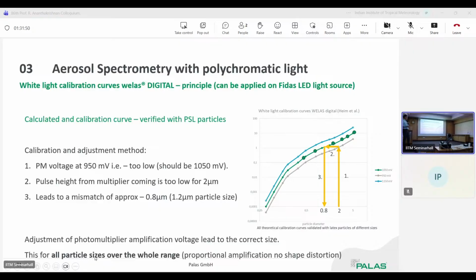So if the signal is too low, for example, for a 2 micrometer particle you would have expected a signal of 2, 3, but it's only next to 1, then we increase the photomultiplier voltage so that we finally get the signal height for that particle according to the latex curve. So this is what we do. We move this calibration curve up and down in order to fit it to one single known size of particles, optical diameter. And then the complete system is calibrated. So we don't need to calibrate each and every size. It's one size which we can use for the calibration.